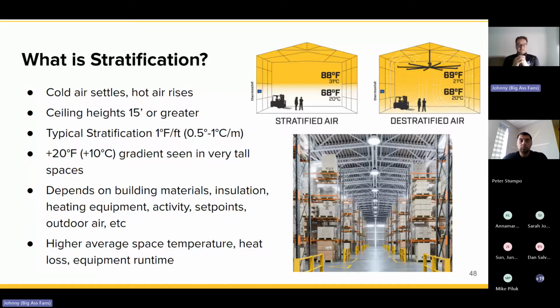Typical delta from floor to ceiling in a building that's 30 feet might be 10, 12, 15 degrees. So if you think about all of that wasted heat energy that's just at your roof deck, having a fan to constantly recirculate that air, you can shrink that delta to about a degree. So HVLS fans, high volume, low speed fans, are not only great at providing cooling, based on the nature and the size of those units, they are going to turn that air over constantly in the building and keep that air mixed. So ceiling heights above 15 feet, you're going to have some degree of stratification that is making it challenging to keep the building comfortable. For everyone, you can know that about a degree per foot of height on the Fahrenheit side. For Celsius, it's about half a degree to a degree per meter of height. So that's effectively the degree of stratification you're going to see.